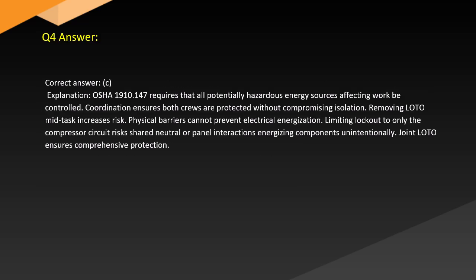Answer. Correct answer, C. Explanation. OSHA 1910.147 requires that all potentially hazardous energy sources affecting work be controlled. Coordination ensures both crews are protected without compromising isolation. Removing LOTO mid-task increases risk. Physical barriers cannot prevent electrical energization. Limiting lockout to only the compressor circuit risks shared neutral or panel interactions, energizing unintentionally. Joint LOTO ensures comprehensive protection.